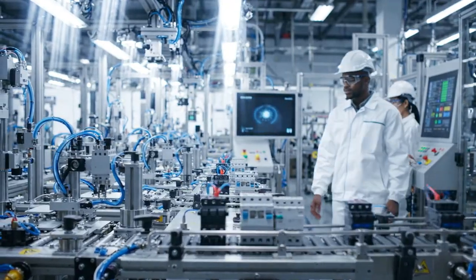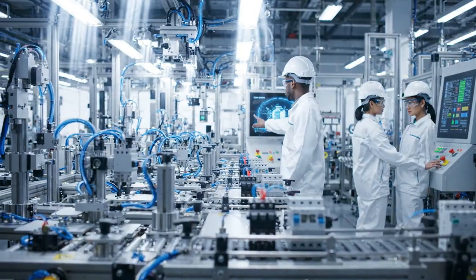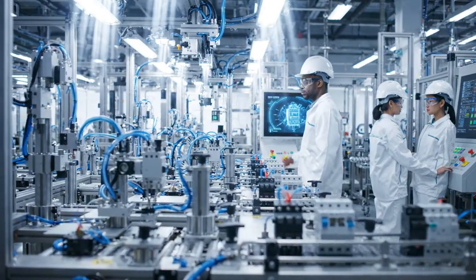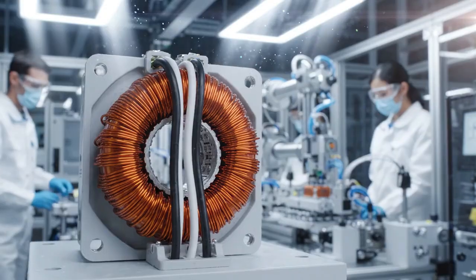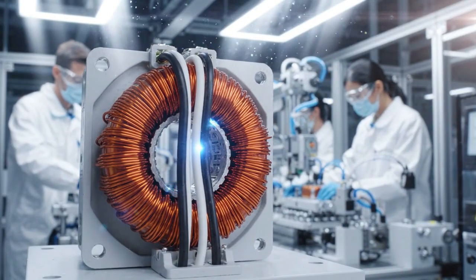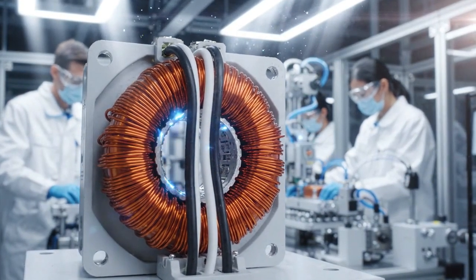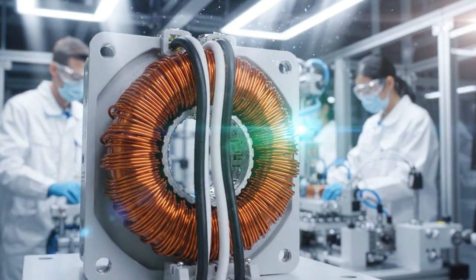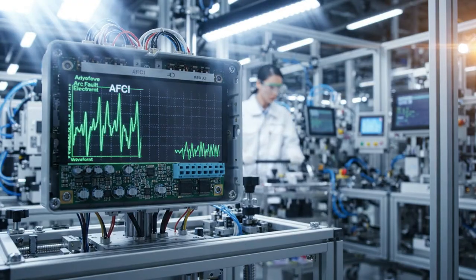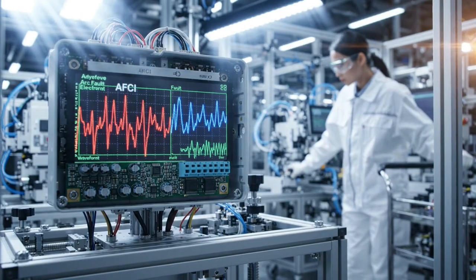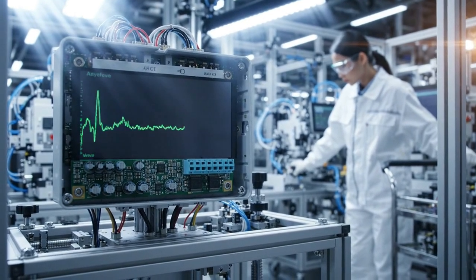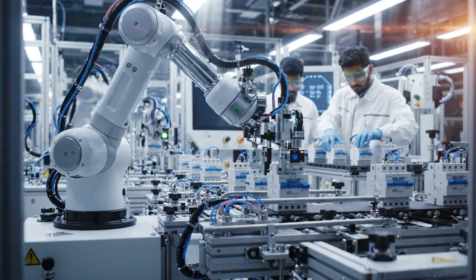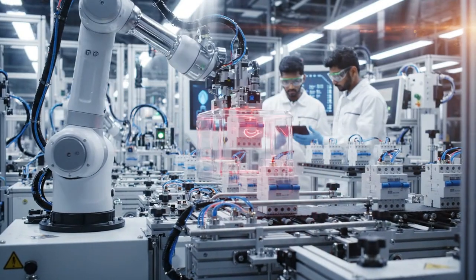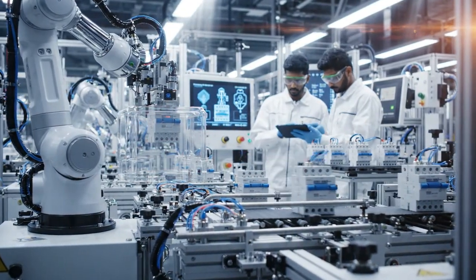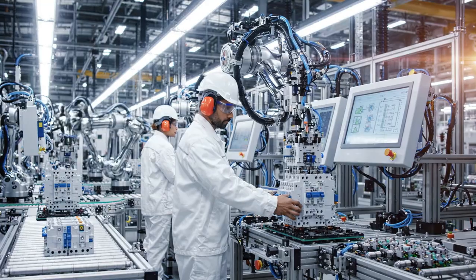GFCI breakers detect leakage currents as small as 5 milliamps flowing to ground through a person, tripping in less than 30 milliseconds, fast enough to prevent electric shock. The differential current transformer is the GFCI heart. It detects the difference between current flowing out and current returning. AFCI breakers use waveform analysis to distinguish dangerous arcing faults from normal arcing events like a motor. Motor protection breakers must allow the high starting current of electric motors to flow without tripping, while still providing fast protection against actual short circuits.